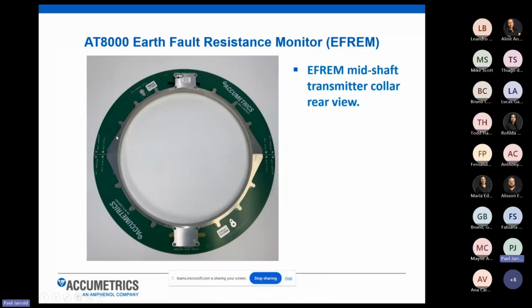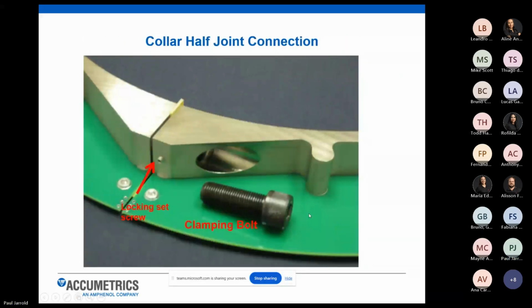And there's high strength bolts that come down and bolt these two half collars to the customer's brushless exciter shaft. And that would be specific to each machine depending on what the diameter of the shaft is. And we will provide a torque spec that these bolts need to be torqued down to hold the system in place. So those are the bolts that go through and connect the two half pieces together. There's a locking set screw for mechanical security that goes in and ties into the threads of the high strength bolt once it's been torqued into place.